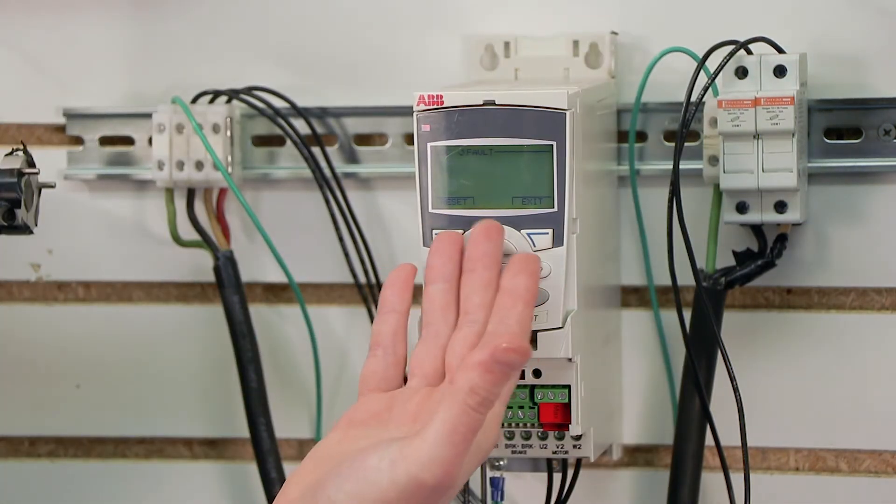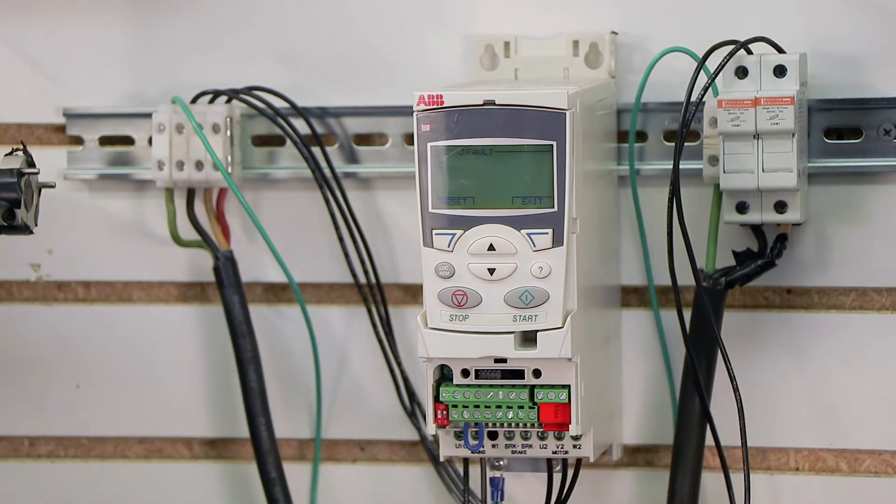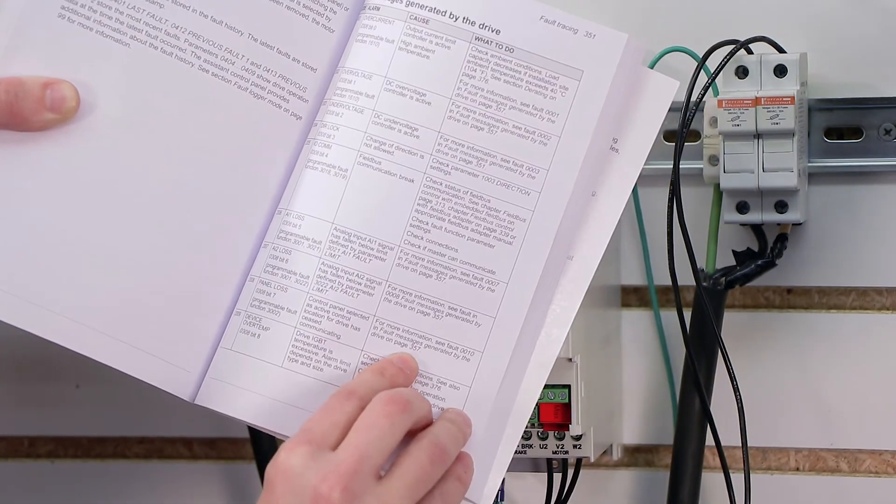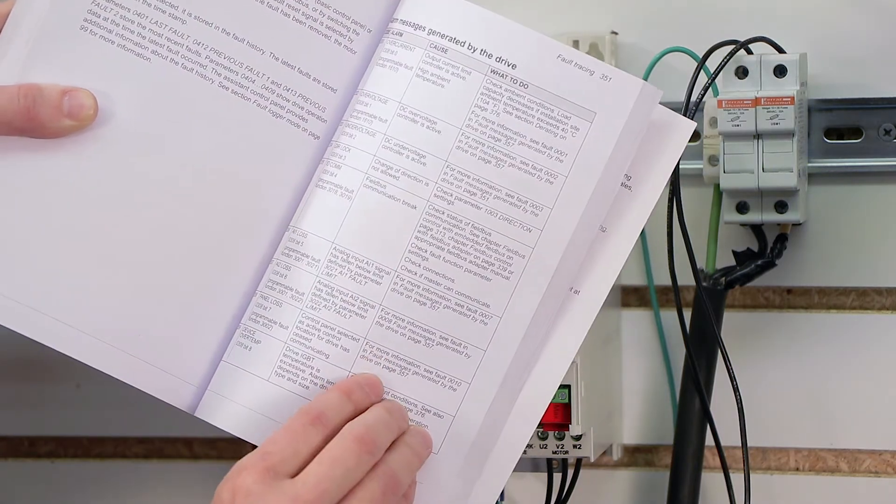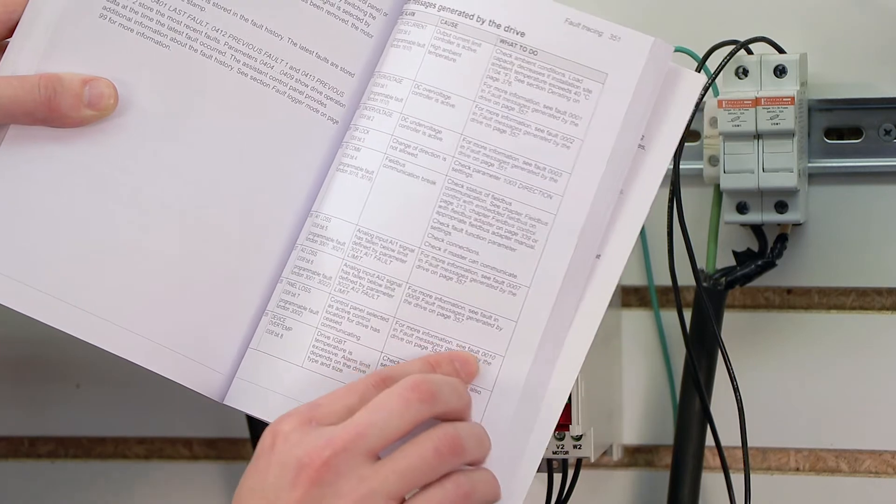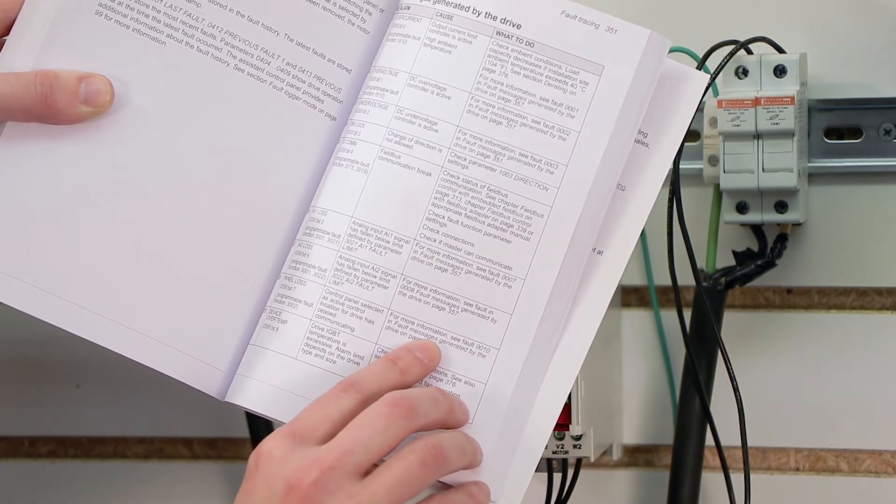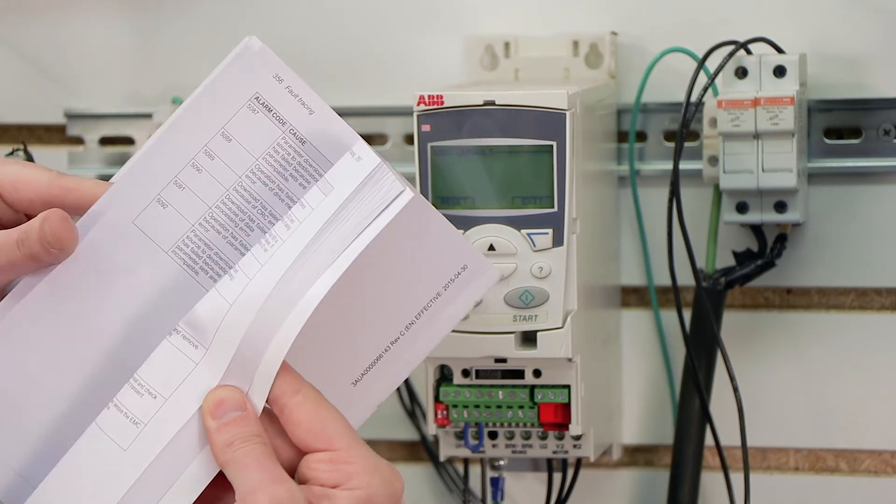So whatever reason it ceased communicating is what I need to diagnose, right? So if I look here on the right-hand side, what's great about this manual is it says what to do, and they will give you some recommended suggestions. This one says for more information, see fault 0010 in fault messages generated by the drive on page 357. So I'm going to go ahead and go to page 357.